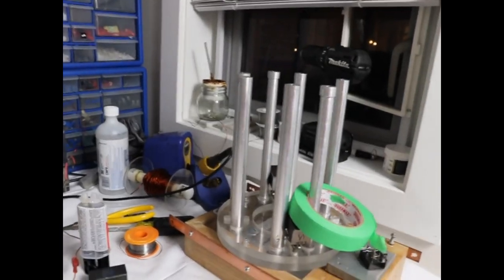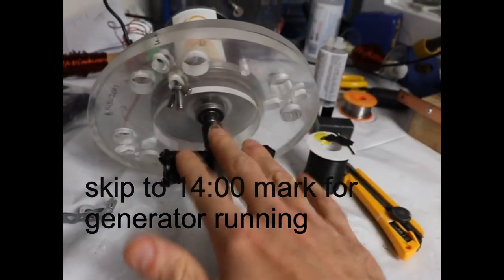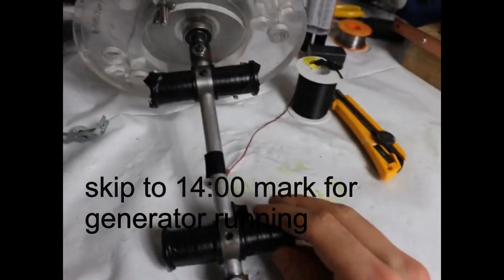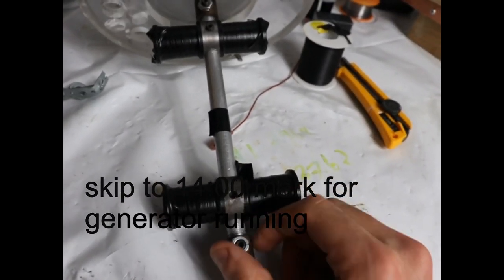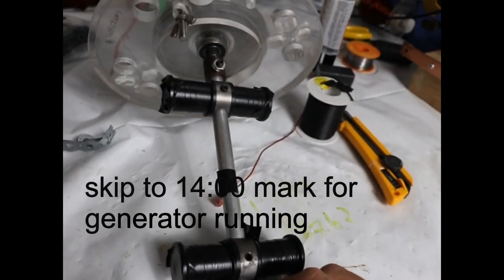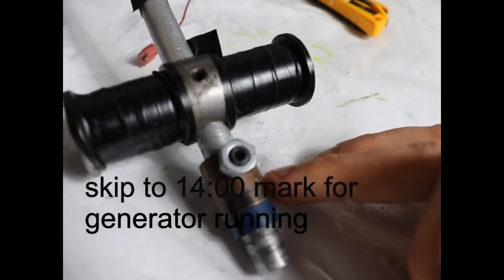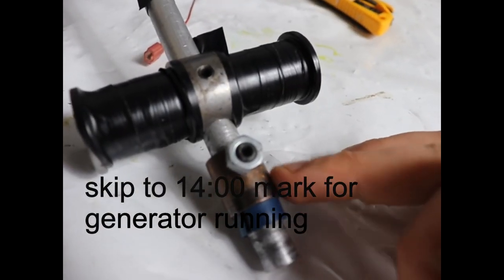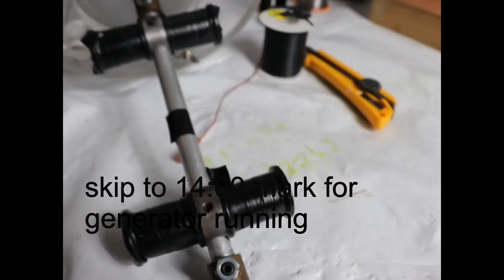Okay, so we have the Kromrey mostly disassembled. We're going to take the coil cores off the shaft and the copper slip rings where the brushes meet and rotate on. You can see the brush marks down here, the carbon starting to wear in nice and smooth, so that's positive.